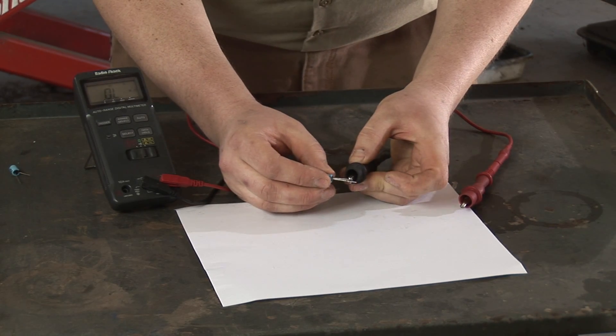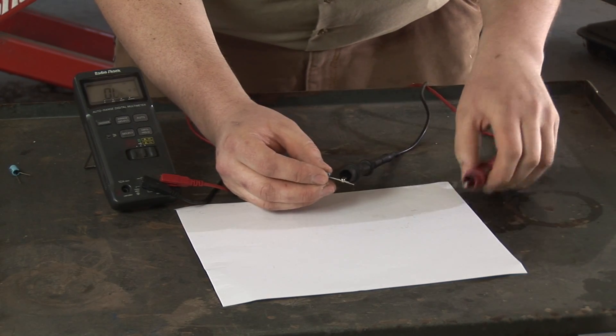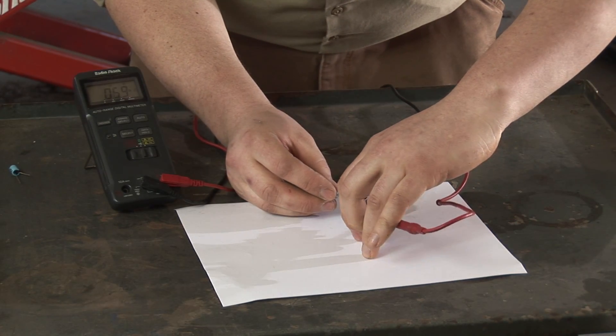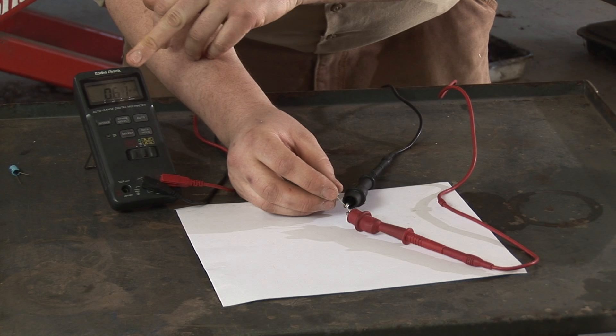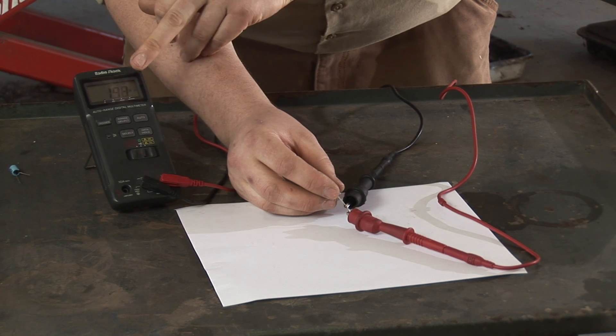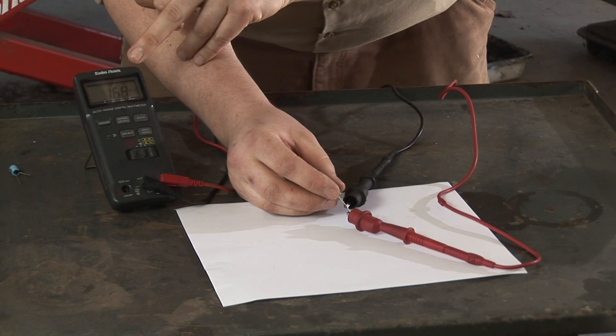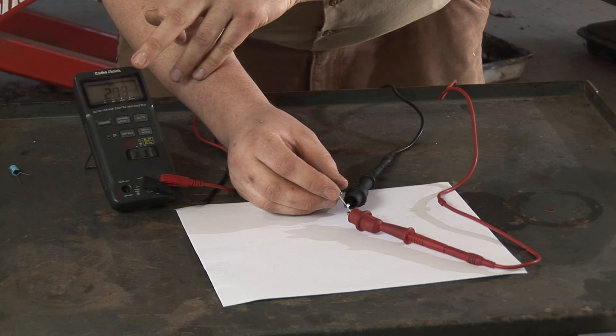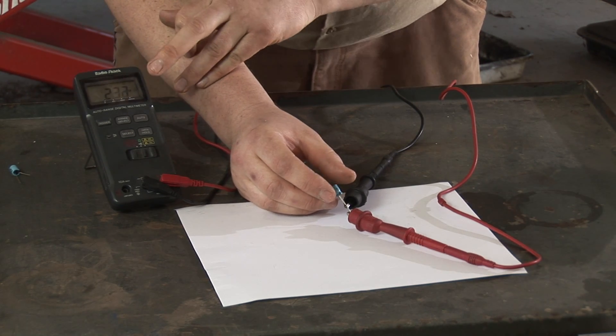Once it's discharged, you hook up your negative lead to the negative side of the capacitor, and your positive lead to the positive side, and what you will see is that the resistance will increase as the capacitor slowly takes a charge from the test voltage coming from the meter. If you see this resistance increase, then that means that the capacitor is functional.